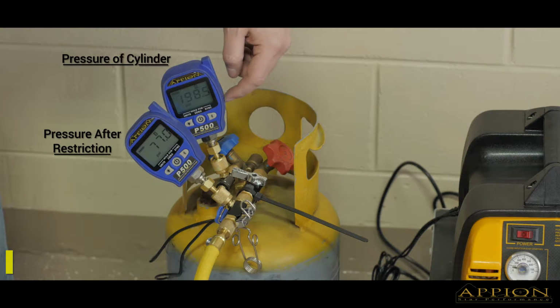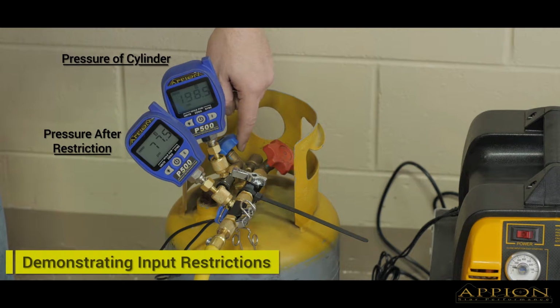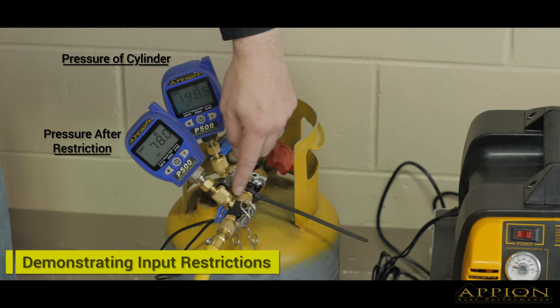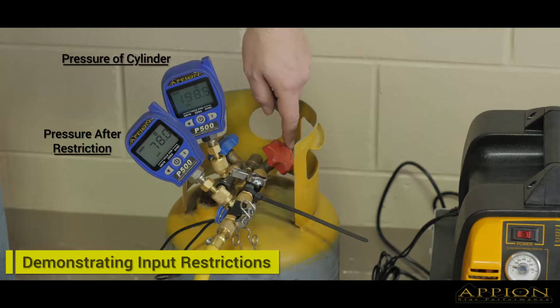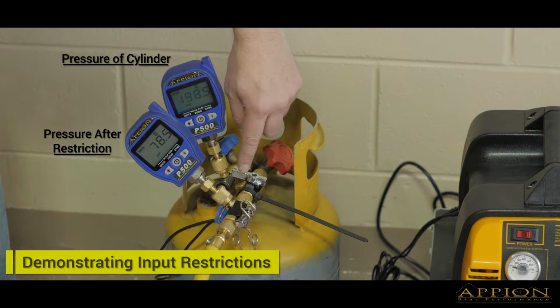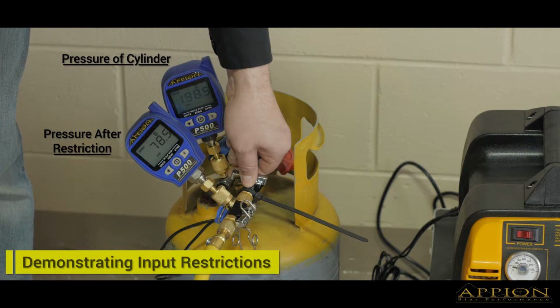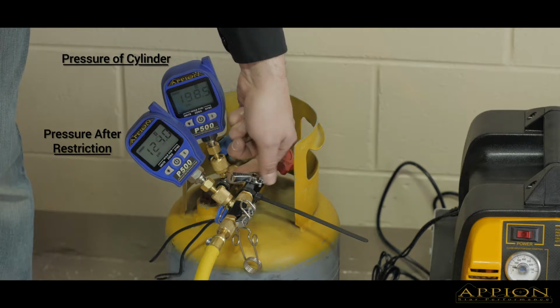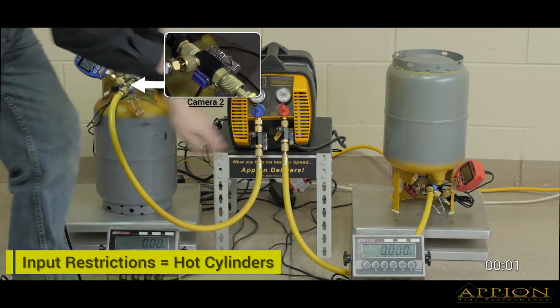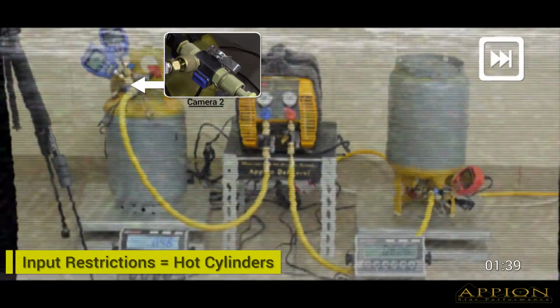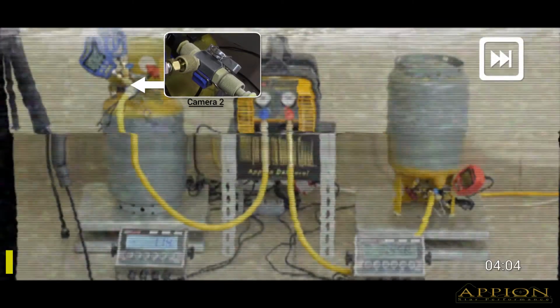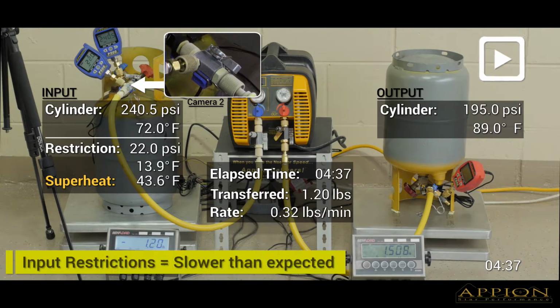To demonstrate, we have a pressure gauge to display the pressure of the tank and another gauge showing the pressure drop due to the restriction. We will be pulling liquid from the liquid port of the tank and using a ball valve to create a restriction during recovery. While the point of restriction grows colder, the transition to vapor begins absorbing heat. When the heat of compression is added to the vapor, the tank gets hotter and recovery gets slower.